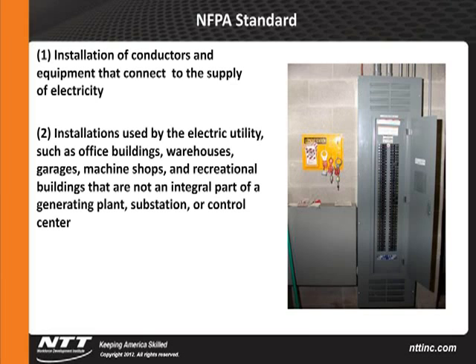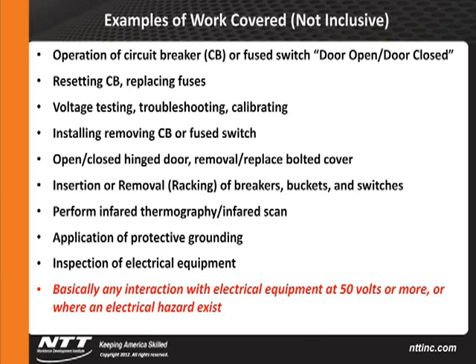But I always get asked, what other types, what does it mean, doing work? Well, right out of the NFPA 70E, these are the types of tasks that are covered then by the standard. It's not inclusive, but it says the operation of a circuit breaker or fused switch, either with the door open or door closed. It's very clear today. Resetting of circuit breakers, replacing fuses, voltage testing, troubleshooting, installing, removing circuit breaker or fused switch, opening a closed hinge door, removal of bolted covers. Why? During that process, things can go wrong.